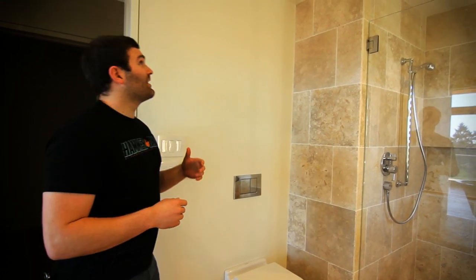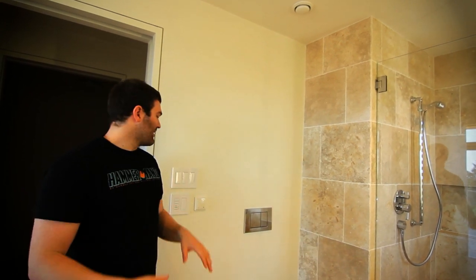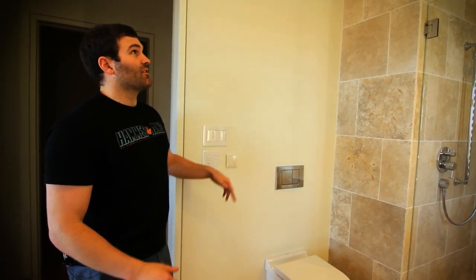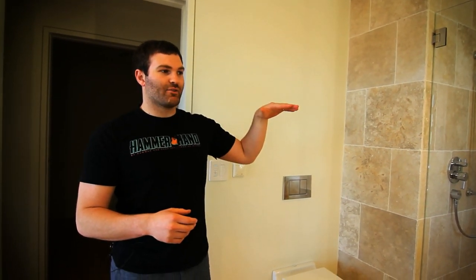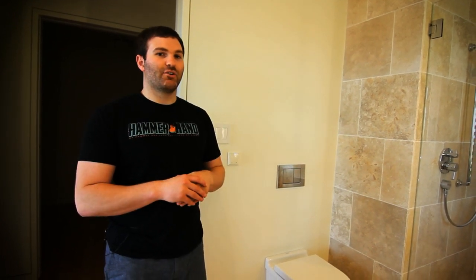If we find that the low flow rate set in the bathroom isn't adequate enough, we have a booster switch here which allows us to access the different speeds, and it also has a timer. If you need an extra boost, the HRV will ramp up and increase the ventilation rate of the room and the whole house in general. Then on the timer setting, after the timer has been satisfied, it will kick the HRV back to its low speed.